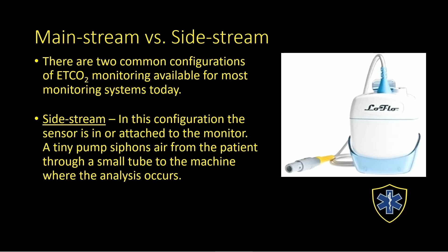Here's an example of two different choices, and as you can see, the one on the left would hook up to the ET tube, and the pump would pump the air back through that connection, the white connection there, into the side stream monitor. However, on the right, we see a nasal cannula. Now, one side of that would hook to the oxygen itself, and this item here would actually hook to the end-tidal CO2 monitor or that LoFlo pump.